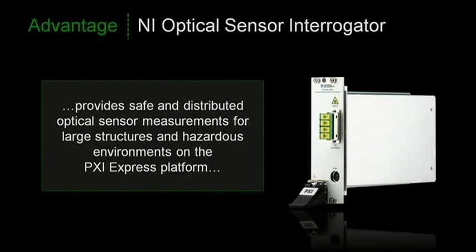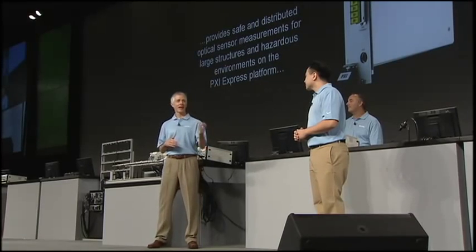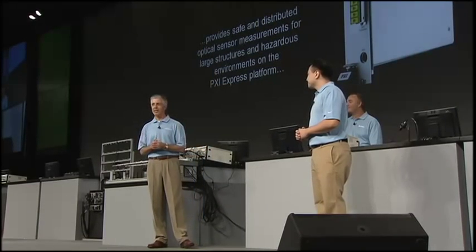As you can see, even after a barrage of electrical strikes, the sensors and equipment were not only left undamaged, but we were able to plot the temperature steadily without any noise. You may not be using Tesla coils in your workplace, but you can easily see how industries and applications like oil and gas and structural health monitoring would benefit from this new technology — especially when dealing with extremely long distances, harsh environments, or high voltages. Philip and Stuart, thank you for introducing us to optical sensing.